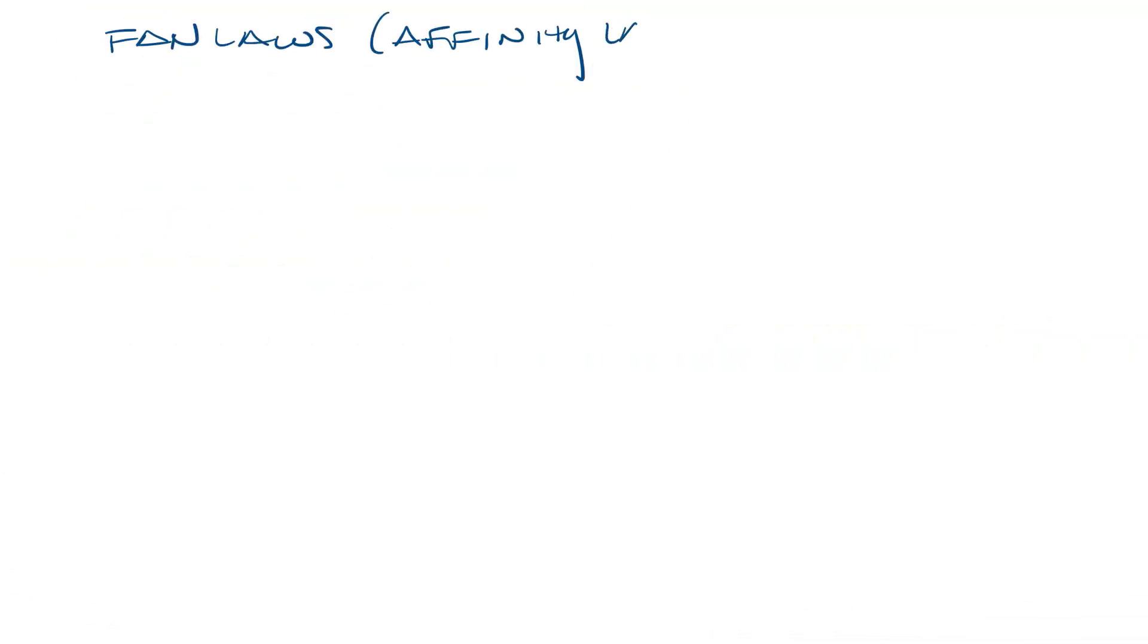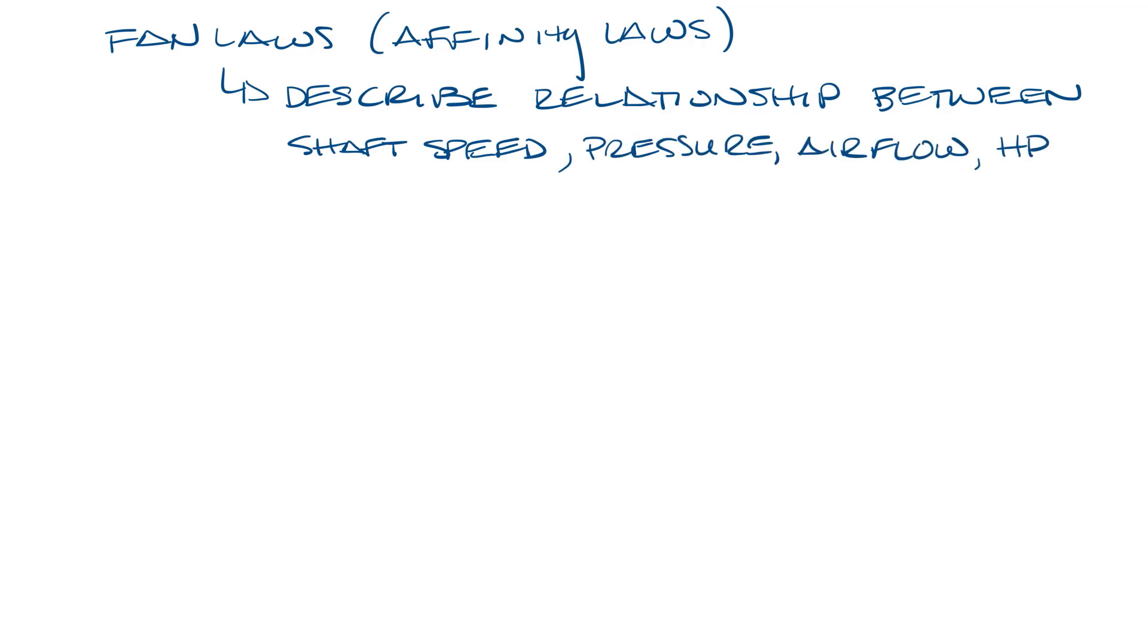The fan laws, also called the affinity laws, describe the relationship between variables involved in fan performance: shaft speed, airflow, pressure, and horsepower. The fan laws assume that air density does not change and that the system the fan is in doesn't change either.